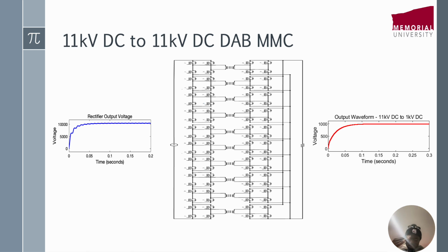The first one will be switched on at a phase shift of 0, then the next one at a phase shift of 30 degrees, the next one at 60 degrees, all the way up to 270 degrees, until we move to the next one and get back to 0 again. So we need to establish that sequence when we are putting them in series so that we can ensure that power is going to flow from one circuit to the other. So that is very important.